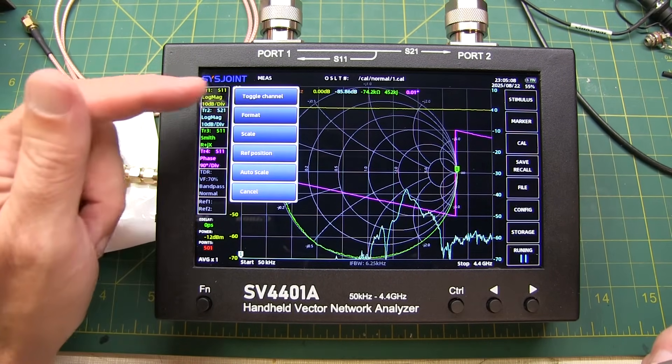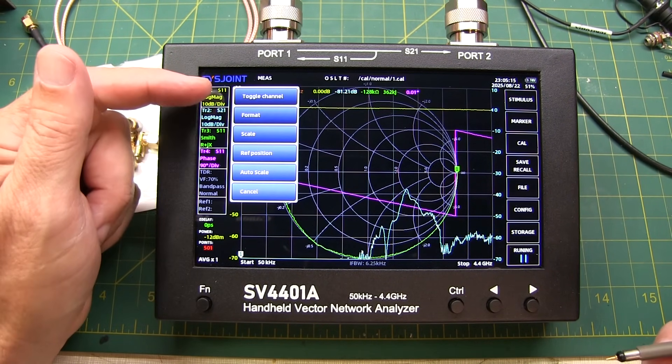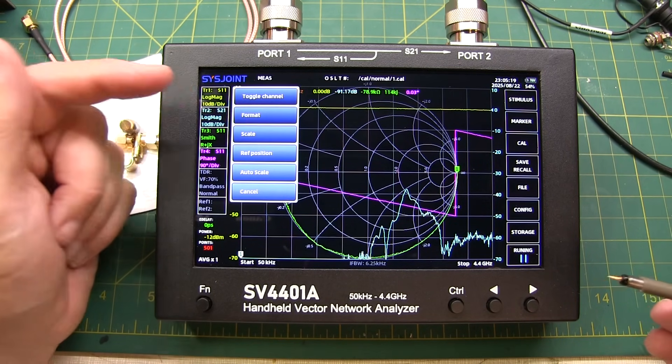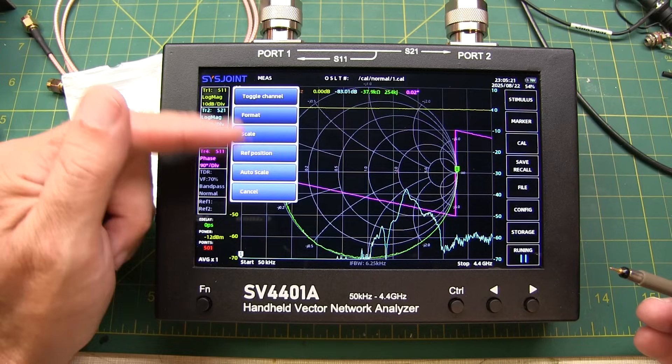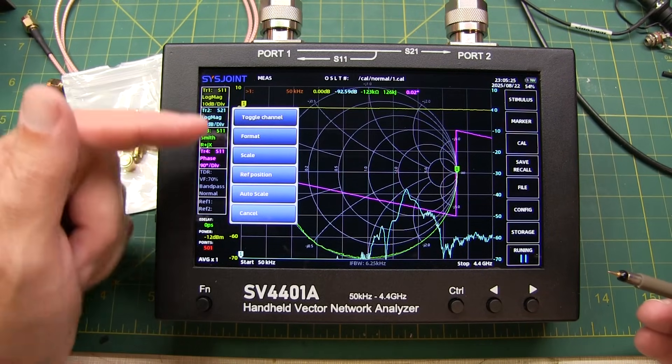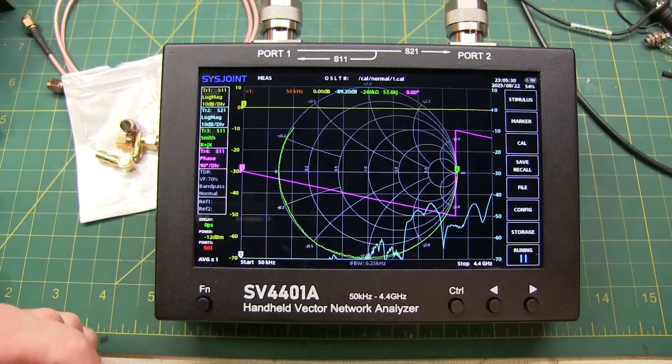Touching and holding brings up the menu for that to switch the port that the trace is connected to, change the format, say from log magnitude to SWR, change the scale, etc. So it's really simple to go and bring up the settings for each of the traces by simply touching and holding on that particular badge.